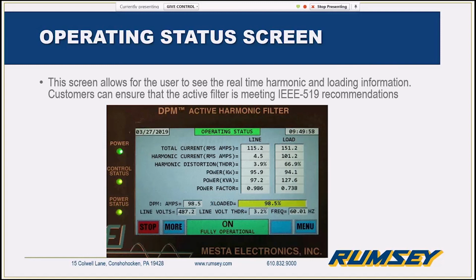That's all that reactive current that we talked about earlier that was being supplied by the generator or the utility, traveling through your transformers and through your cabling, that now isn't happening. So that's that increase in system capacity. And you can see kW, kVA, power factor, and the percent loading. I don't have it on here, but if you click that More button down there, you'd see a per-phase breakdown of all of this information.